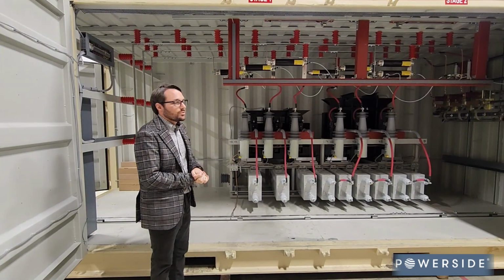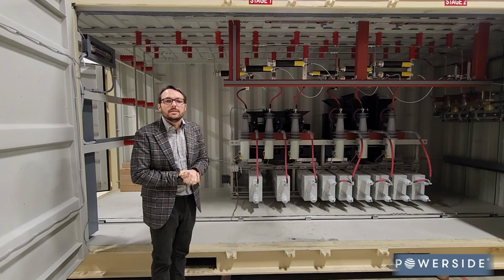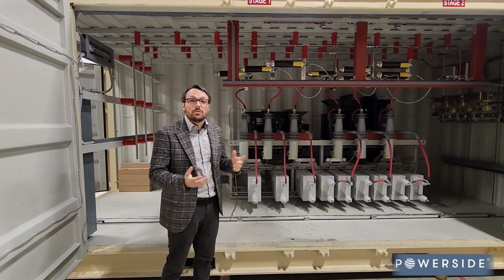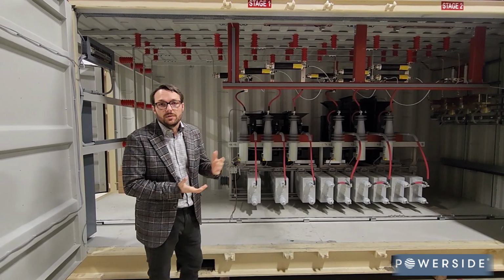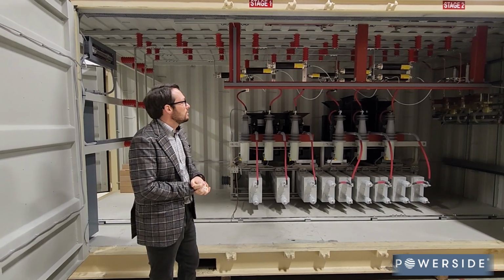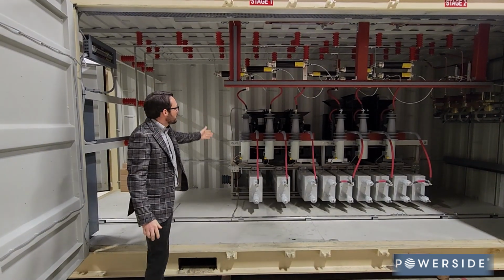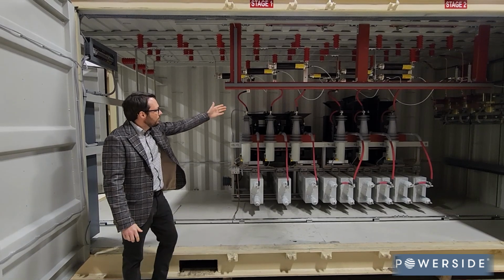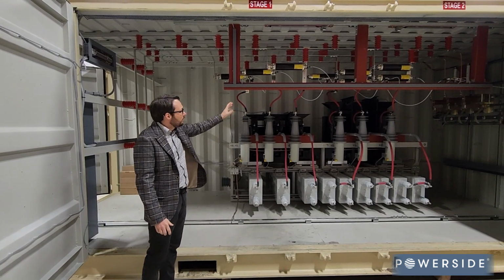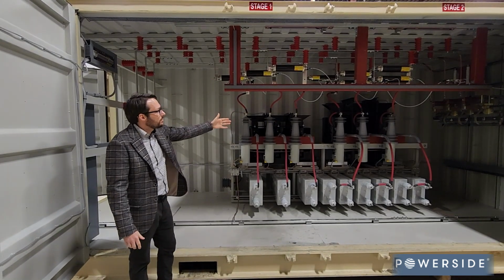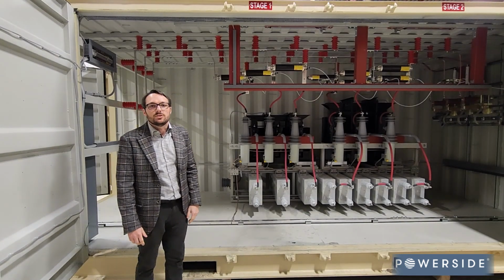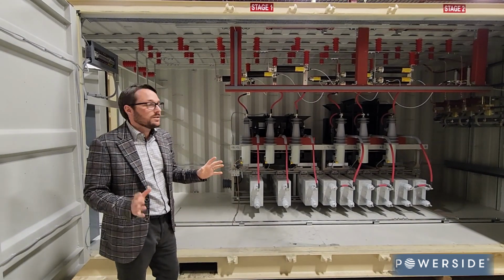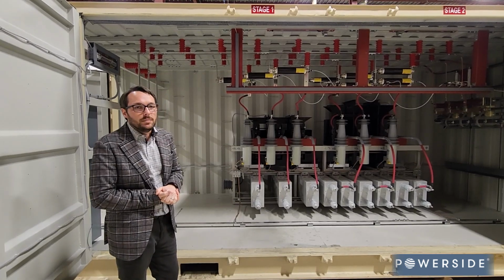Fairly basic. The control, which we'll look at in a minute, is power factor control, and we have the ability to, of course, manually control it. You'll notice here we've got our reactors, which then feed our capacitors, and then in front of that, of course, are our vacuum switches. So again, a 2-stage configuration, not extremely complicated by any means.